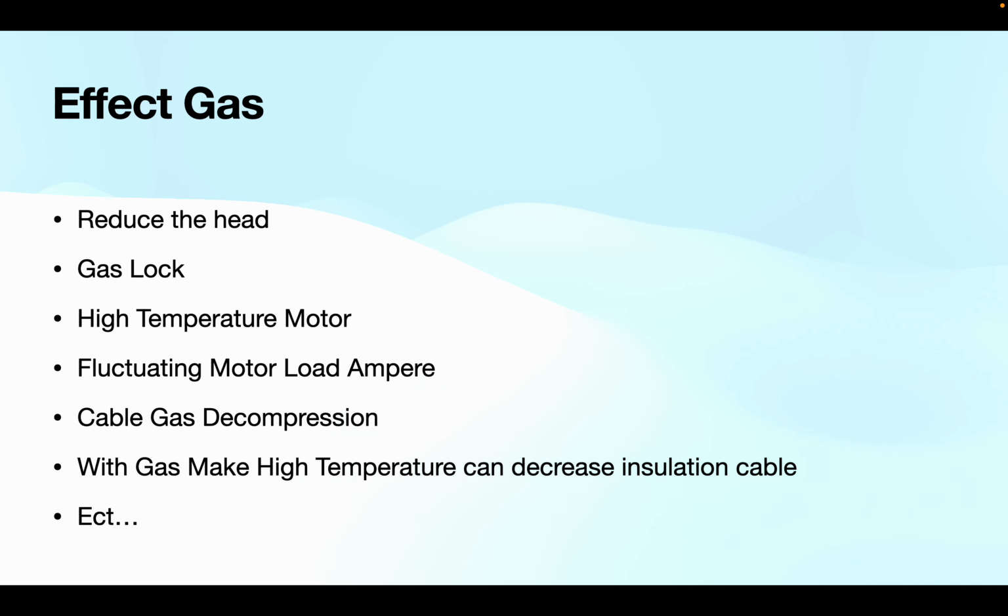If an amount of gas comes to the intake and into the pump, it can cause gas lock. Only gas is inside the pump, so there is no flow, and this also makes the motor temperature high, because with gas lock there is no flow in the casing of the motor to cool it.